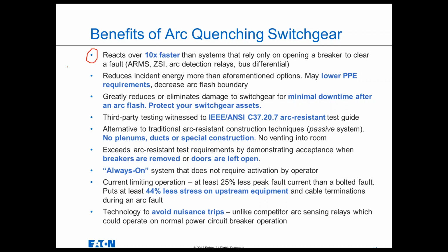And the incident energy is actually reduced to such a low level that the switchgear will exceed those arc resistant test requirements by passing the arc resistant test, even if a door is open or a breaker is removed. So typically when you perform an arc resistant test, C37.20.7, per that test guide, you place cotton indicators that are calibrated to burn at about 1.2 calories per centimeter squared. You place these cotton indicators 4 inches in front of the switchgear around all 4 sides. And then you intentionally ignite an arcing fault inside that equipment. And if one of those cotton indicators burns, it's a fail. That sort of represents one of us standing in front of the switchgear in just a cotton shirt, which obviously is a no-no under any circumstances.